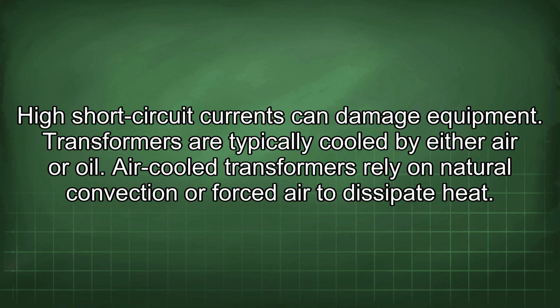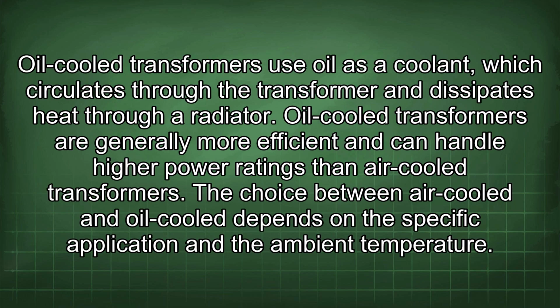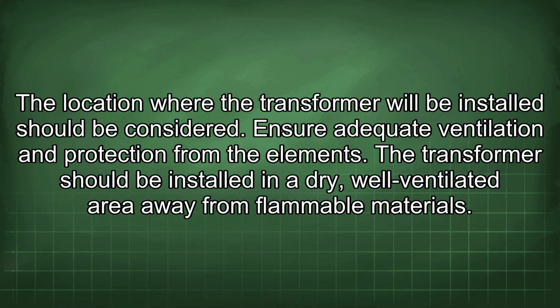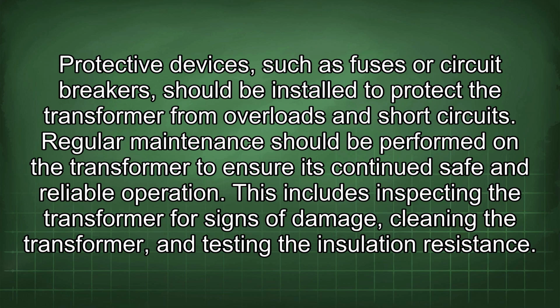Transformers are typically cooled by either air or oil. Air-cooled transformers rely on natural convection or forced air to dissipate heat. Oil-cooled transformers use oil as a coolant, which circulates through the transformer and dissipates heat through a radiator. Oil-cooled transformers are generally more efficient and can handle higher power ratings than air-cooled transformers. The choice between air-cooled and oil-cooled depends on the specific application and the ambient temperature. The location where the transformer will be installed should be considered. Ensure adequate ventilation and protection from the elements. The transformer should be installed in a dry, well-ventilated area away from flammable materials. Protective devices, such as fuses or circuit breakers, should be installed to protect the transformer from overloads and short circuits.